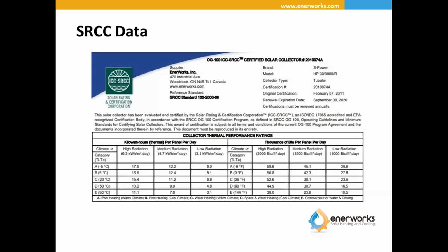Now, I tend to use category D in California because it's somewhere in between the commercial hot water heating and warm water heating. Commercial water heating is always a higher temperature application than domestic hot water for residential systems. And I found this to be very close to any simulations that I've seen. So I typically would use the 44,900 BTUs per day.